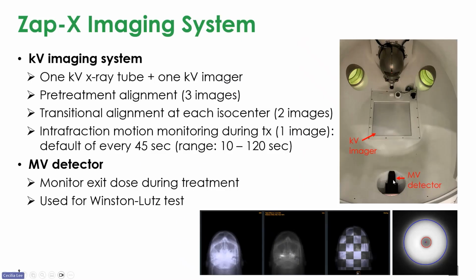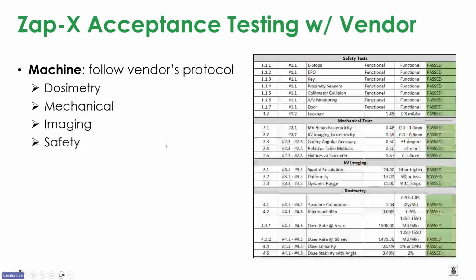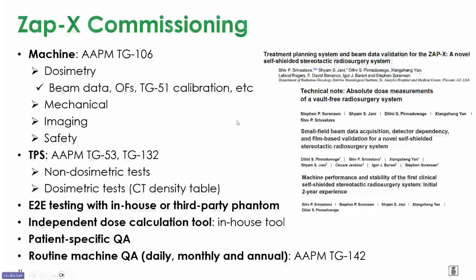And this is also used for Winston-Lutz test and analysis. So after installation is done, you can perform acceptance testing with the vendor. The vendor has a protocol, so you can follow their protocol. There's a dosimetry test, mechanical test, and imaging and safety test. And then you do commissioning.